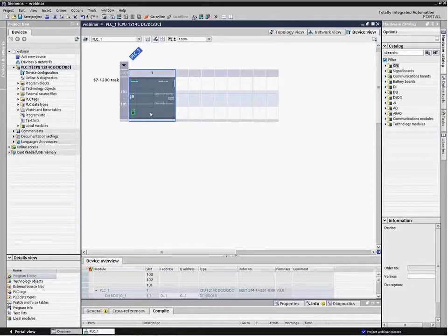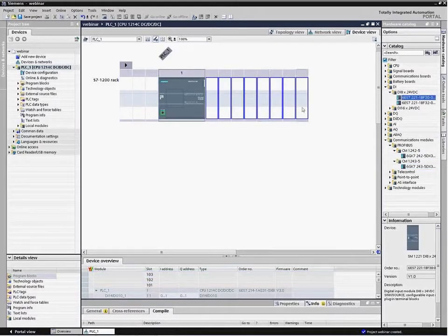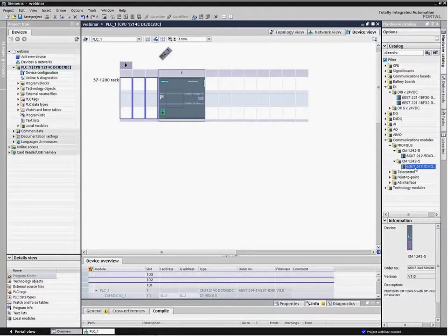So in other words, if I'm doing a hardware configuration, as we jumped into now, it's going to give me all the different options of hardware that I could add to this processor. For example, if I wanted to add a Profibus module into the CPU, then it gives me the different flavors here. There's a slave module and a master module. If I click on it, it tells me which slots it can go into. In the case of the 1200, it's kind of a unique feature in that it puts any communication or specialty modules on the left side of the processor. And why? So as not to use up any of the I/O areas to the right side. So if I click on a digital input module, those are available to go on the right side. And if I do the communication module again, it can go on the left.